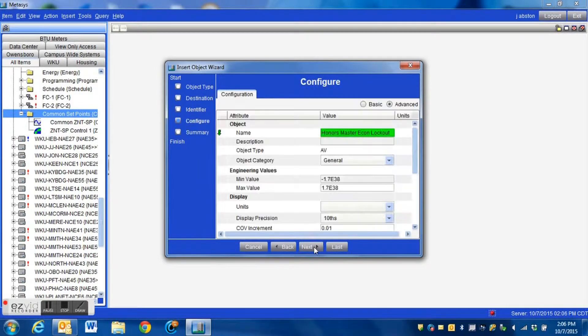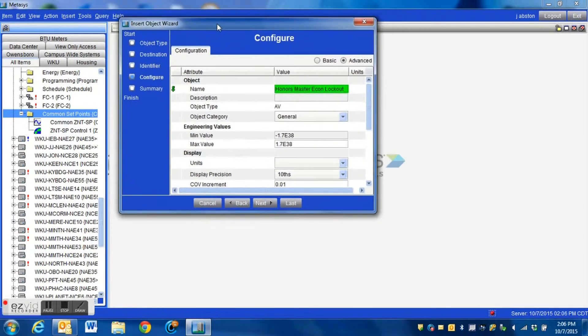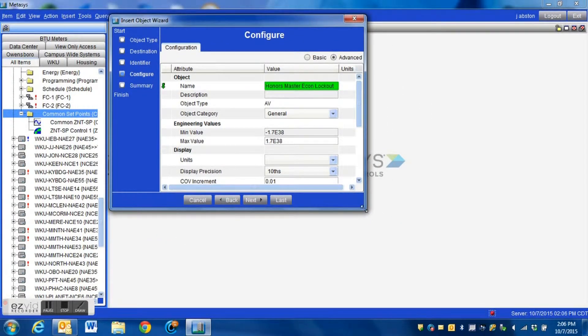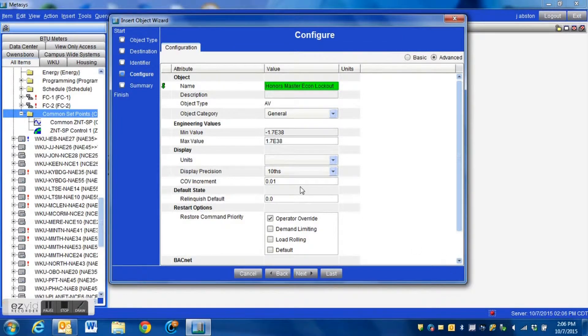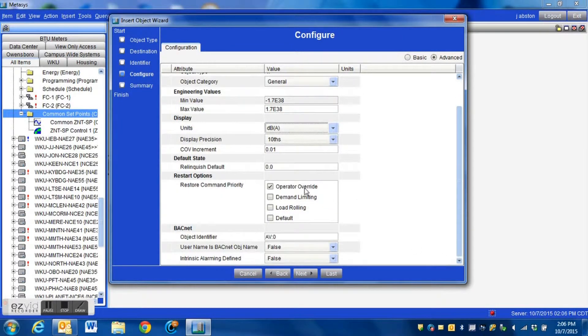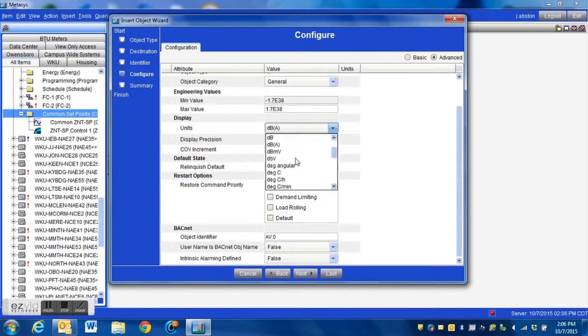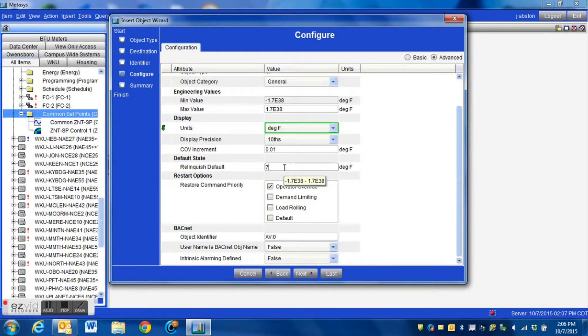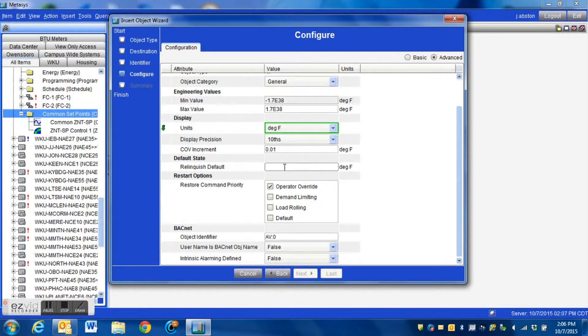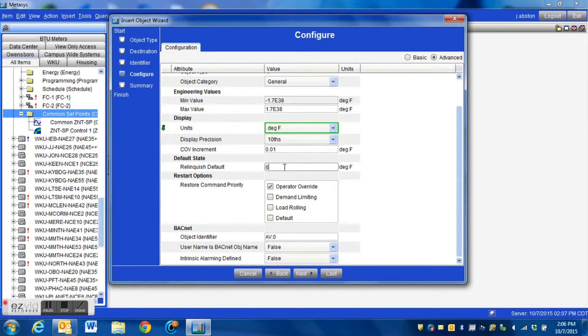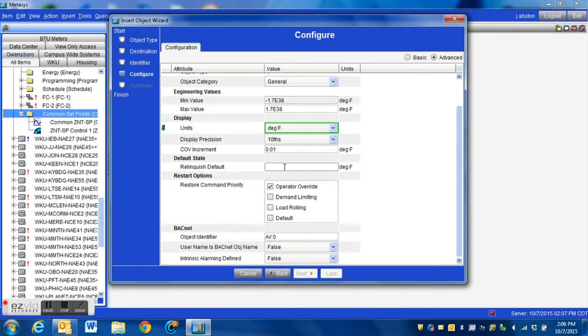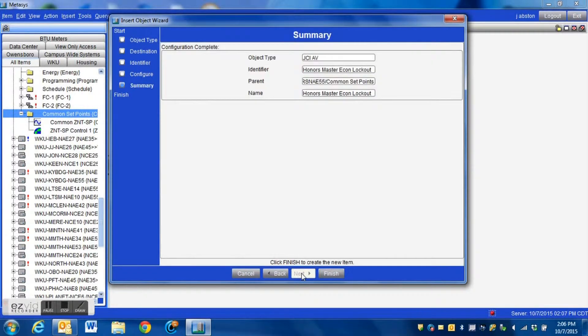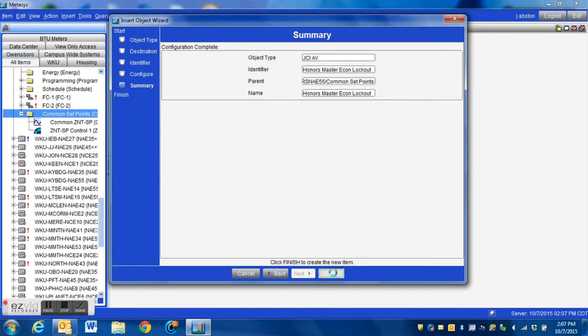Once we have that named, in this configuration screen we need to set up our units. We're going to set this to degrees Fahrenheit since we are using temperature. We're also going to put a relinquish default value in this, that way if something were to happen if the controller were to reset or something it would go back to this value, just a little extra security on setting one of these up. We're just going to throw a value in here, we'll say 60 degrees, just a good round number, hit next, this is a review screen, we just hit finish.